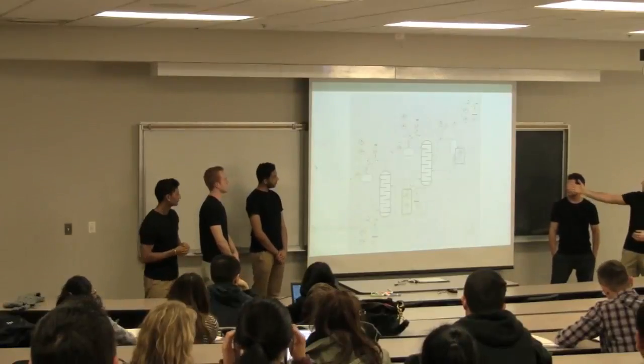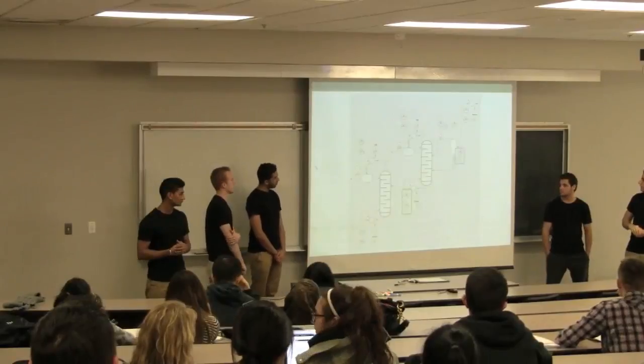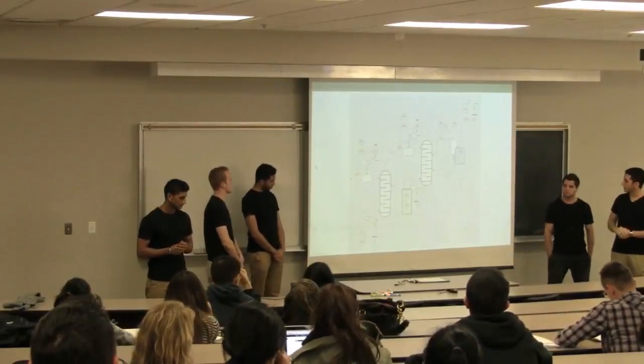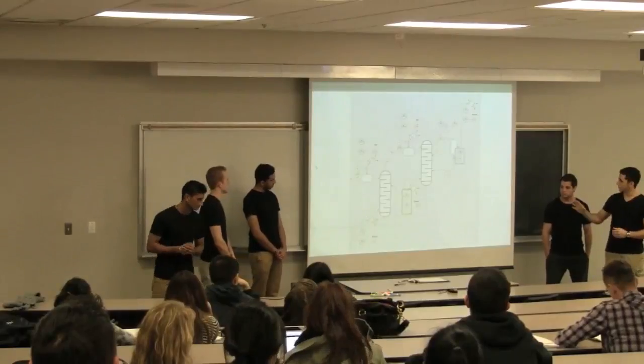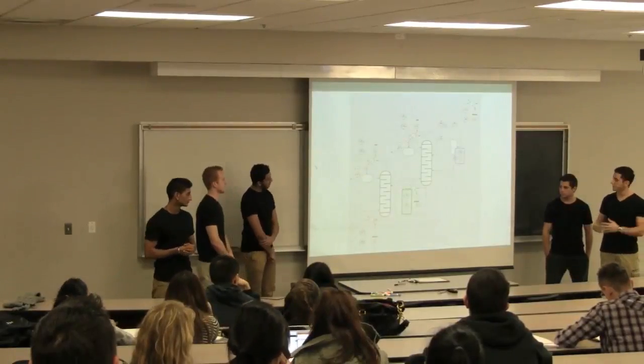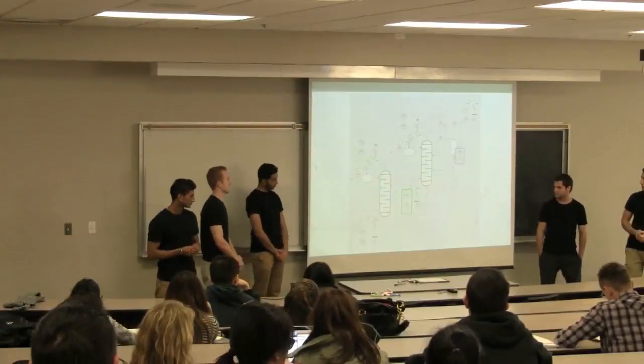The blue box here shows a level controller, which adjusts the level inside the flash tank by manipulating a valve for the liquid stream out. And the green box is a temperature controller implemented around a heat exchanger, and it controls the steam going to the heat exchanger to adjust the temperature of the material coming out of the heat exchanger.